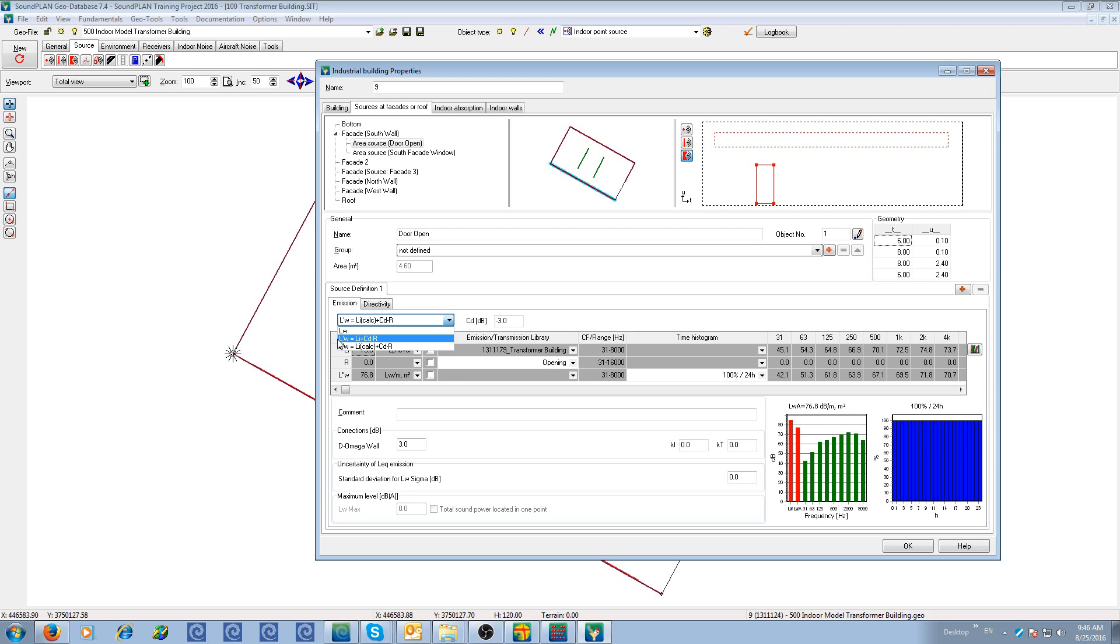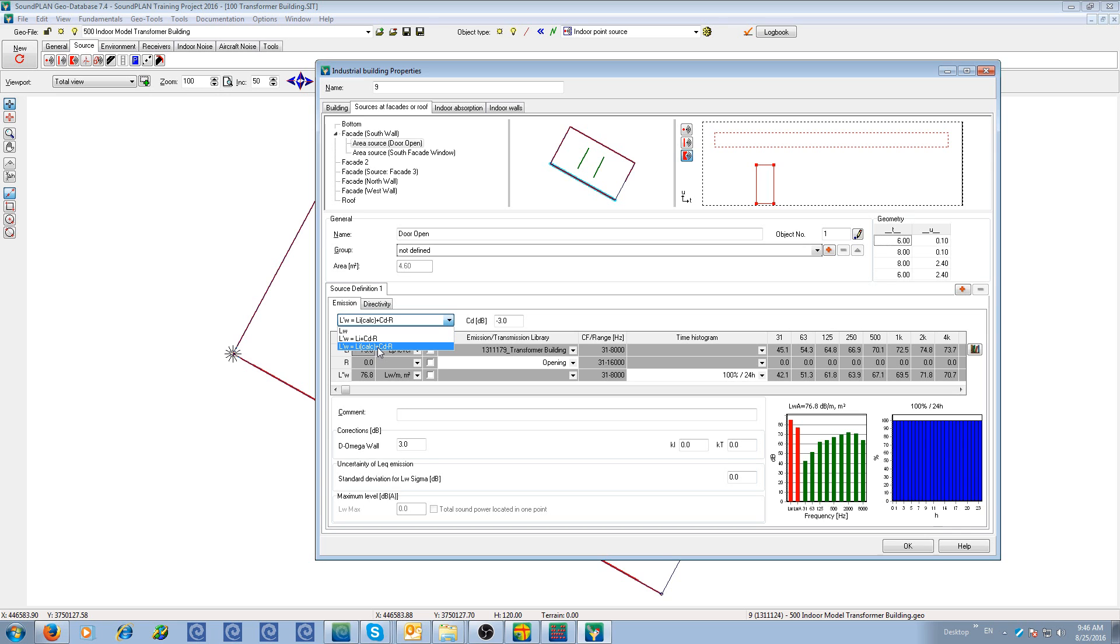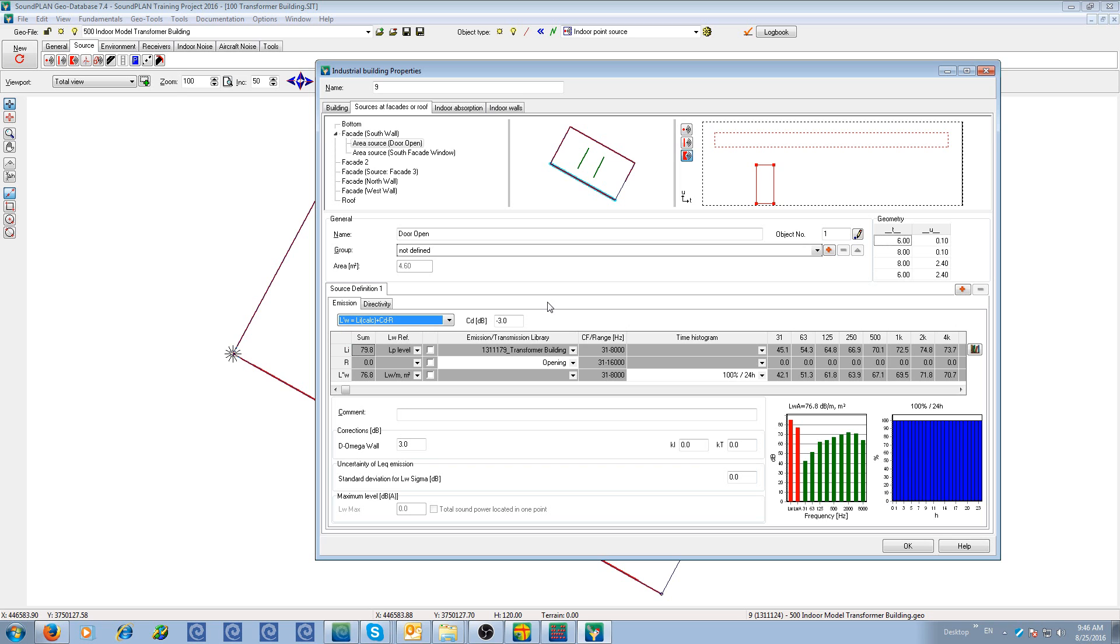In this case, we actually will do an interior noise model. So we use the third option, L'W. And this is the Li calc, plus CD, the room correction, minus the transmission loss. The room correction depends on how absorptive the room is. The more absorptive the correction tends to go to zero. Very reverberant room will get a correction of up to six decibels. So minus six is the highest correction. It is recommended by the standard.